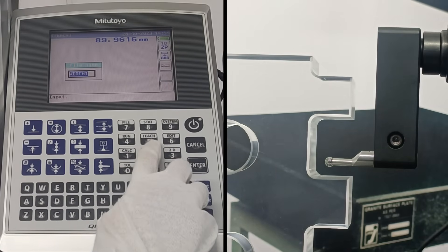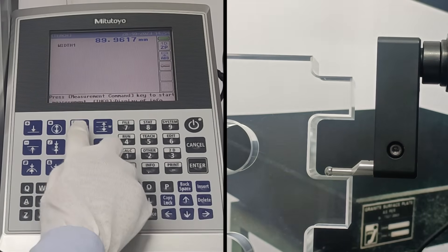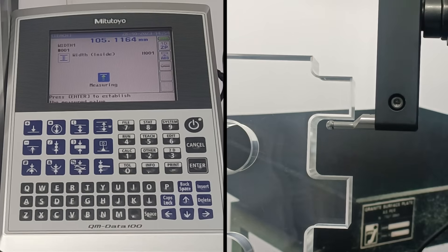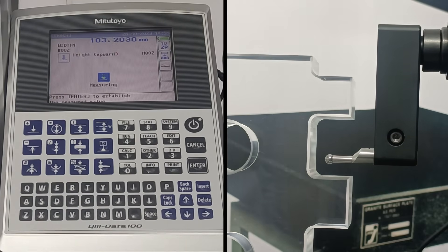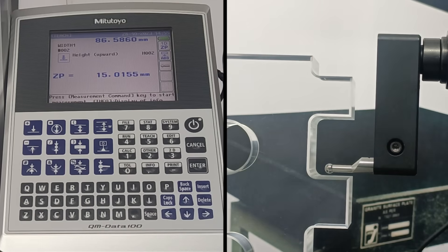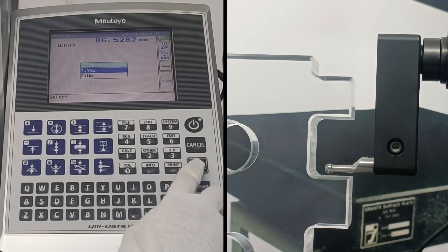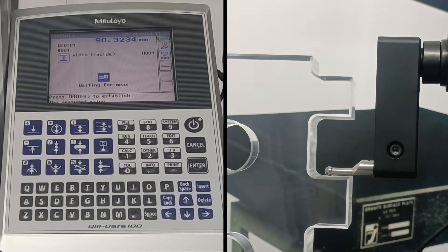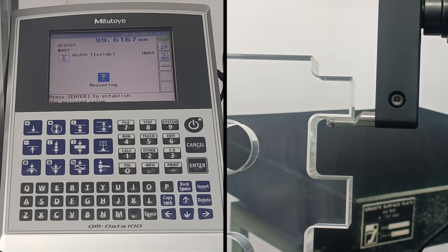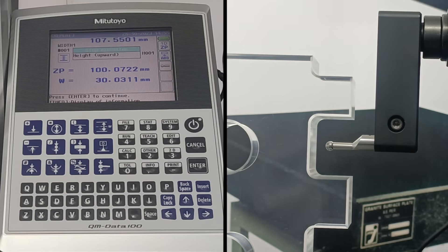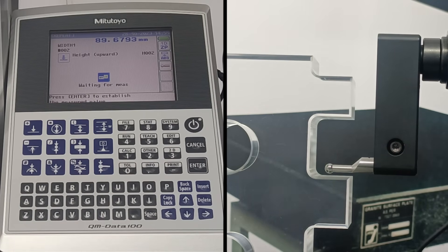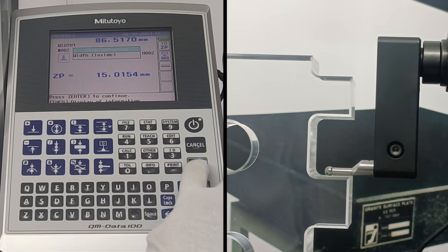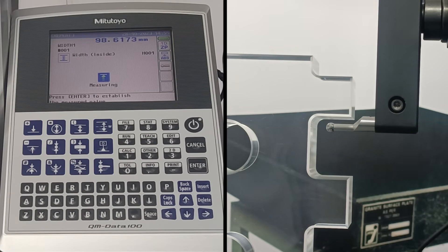Let's see how to use teach and run options. Press teach and enter an operation name. I have selected width. Measure the width of the component. I would also like to add height operation. Now a part program is created. Let's run the command. Keep the repetition depending on usage. Now the program runs automatically. Enter for height measurement. Confirm the repetition.